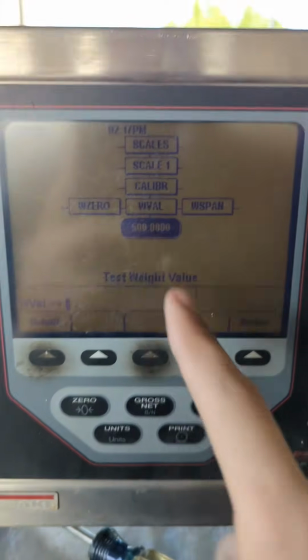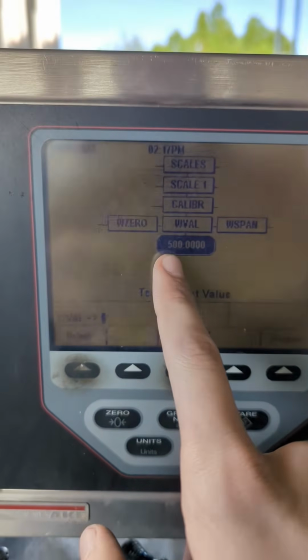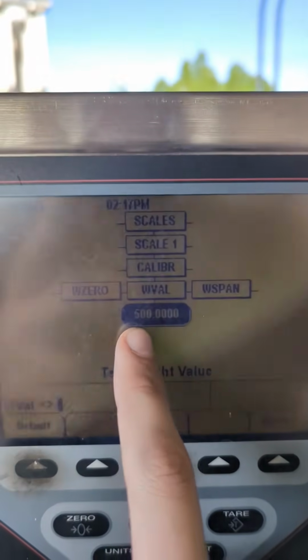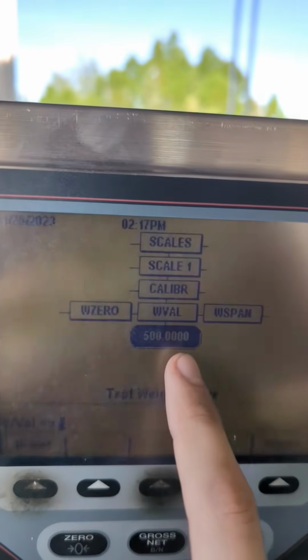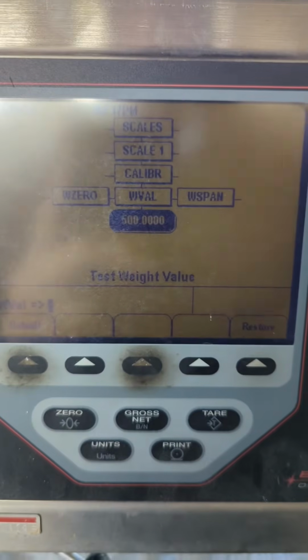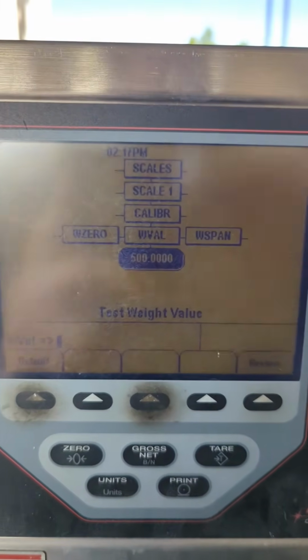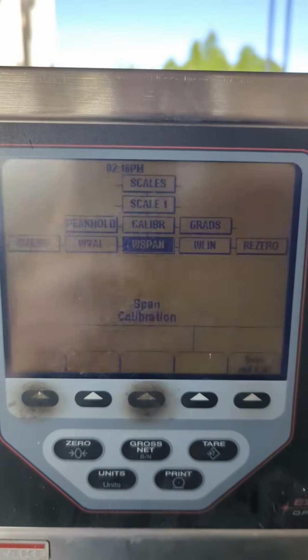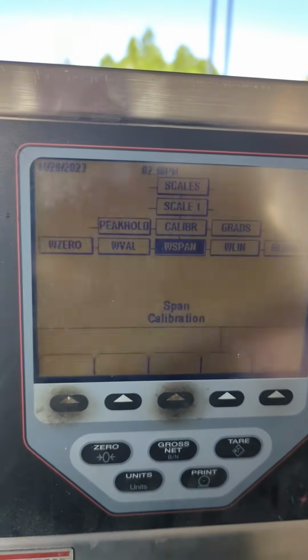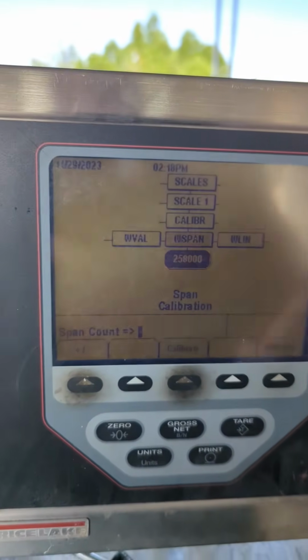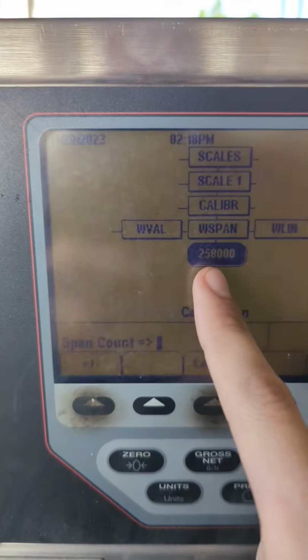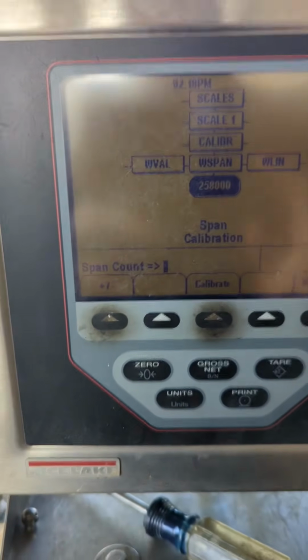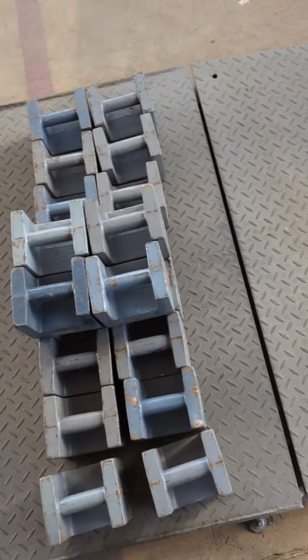You can go up and over to W value. You just want to make sure that whatever weight you're putting on the scale to calibrate lines up with that. So that's 500 pounds right there, 500.000, but that's 500 pounds. As long as that's good, you can just go back up, go over to W span. Now you go down, and that's going to be the count of what's on the scale. You are going to make sure you load up the weights. So I'm going to do that real quick.